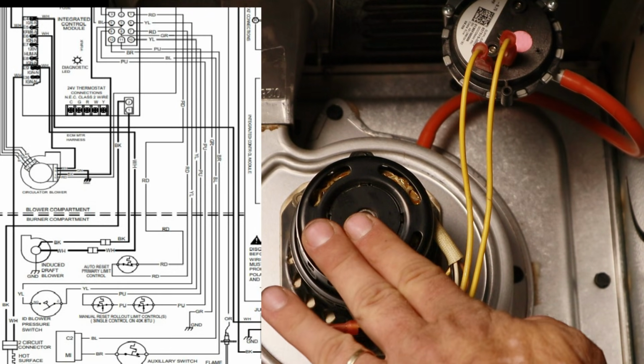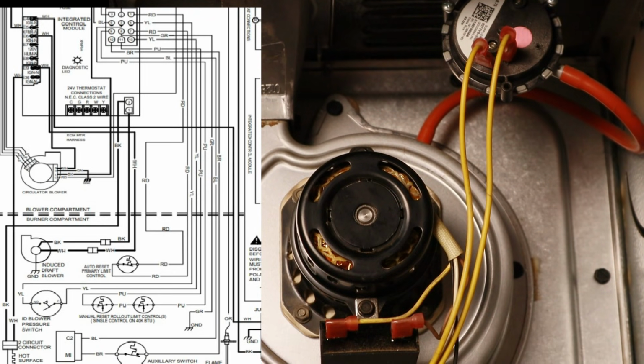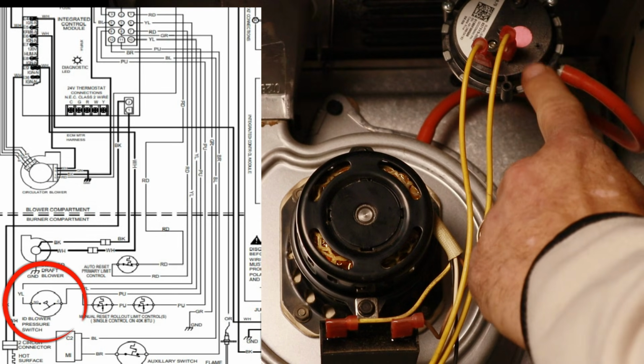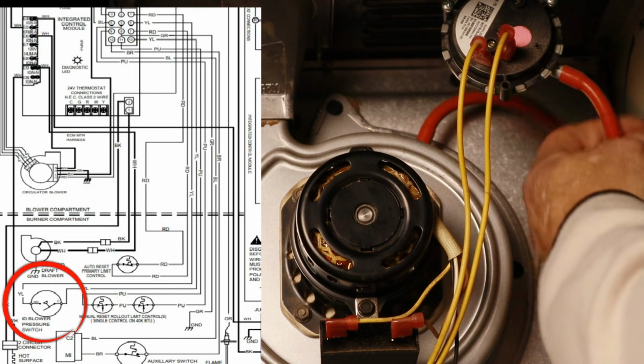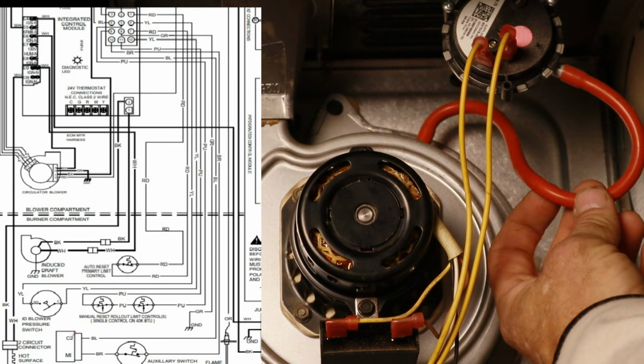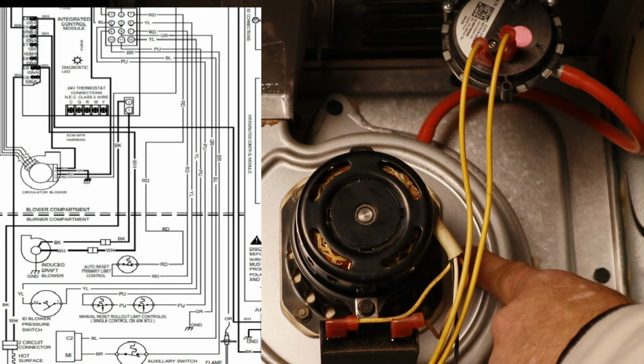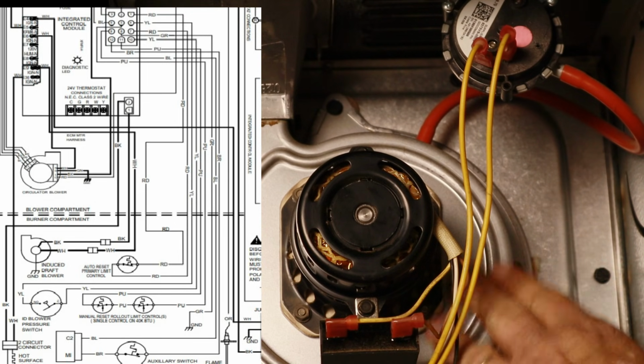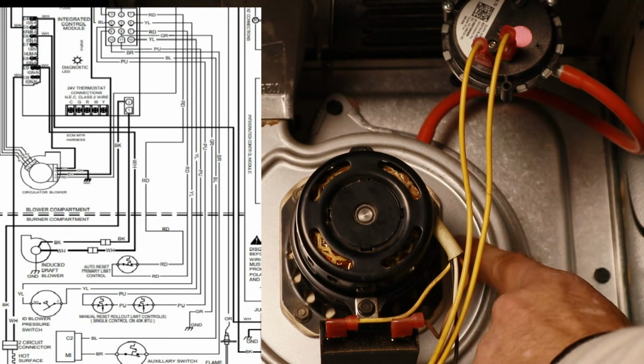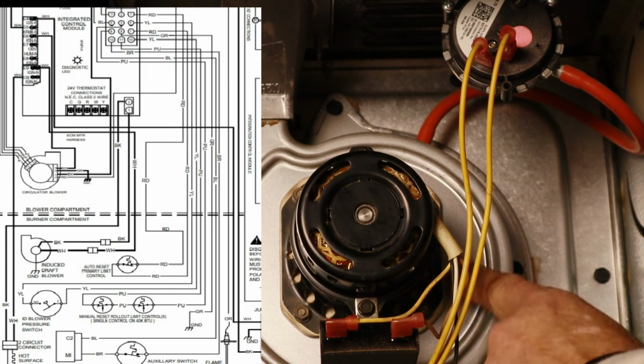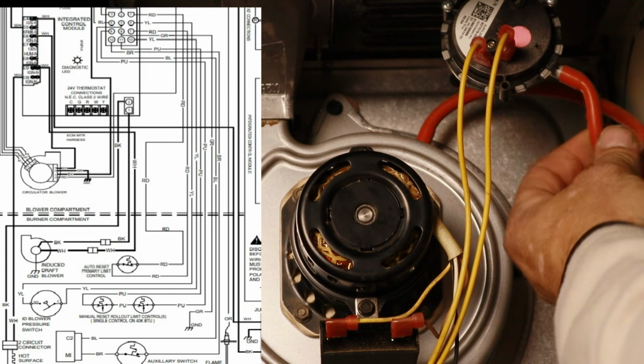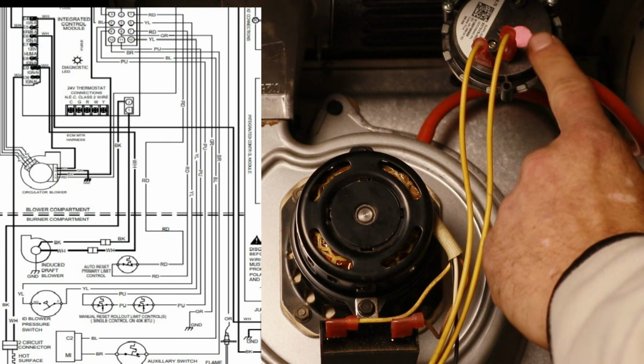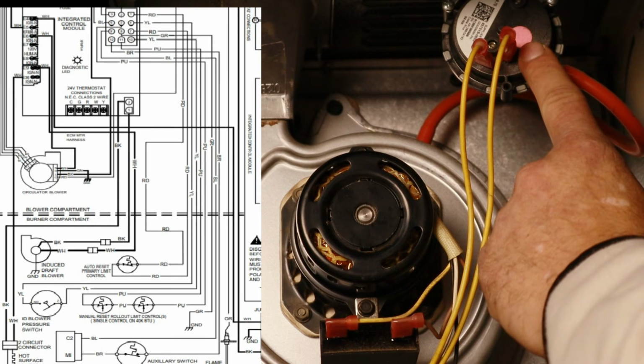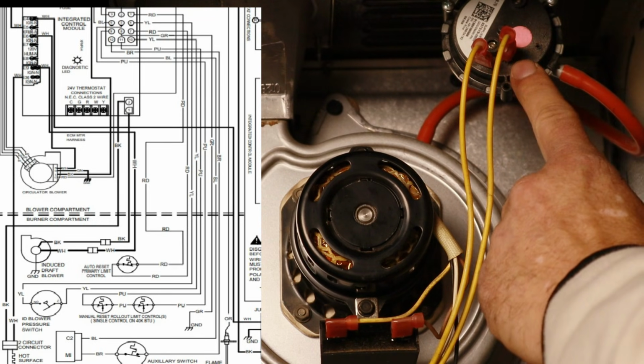Now, once our inducer motor comes on, the next step in the sequence of operations is for this pressure switch to close. You can see there is an orange tube here connected to the casing of the inducer motor. So what happens is this inducer motor runs, it creates a slight pressure drop in this casing, and that pressure drop pulls on a diaphragm inside of our pressure switch, and that closes the switch.